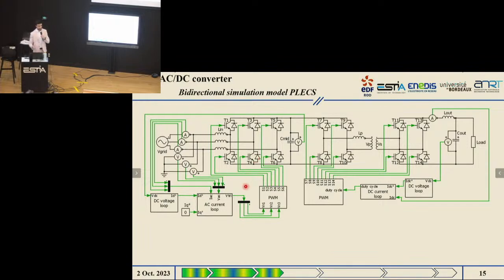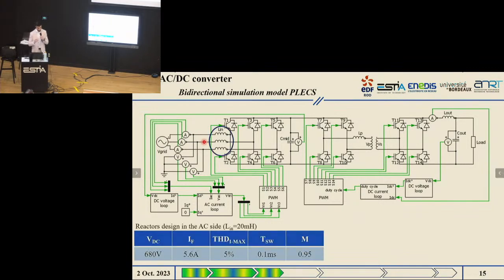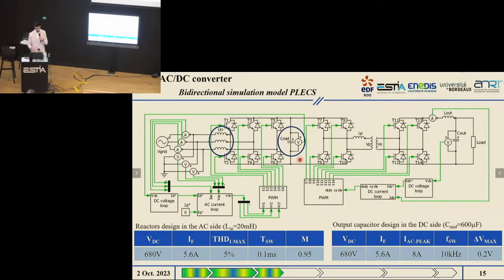Following a certain number of design rules, we were able to size the input filter so the reactors limit the maximum THD to 5%. The same reasoning was applied to develop and implement the output capacitive filter, where we tried to limit the maximum voltage oscillation in the intermediary DC bus to 0.2 volts.